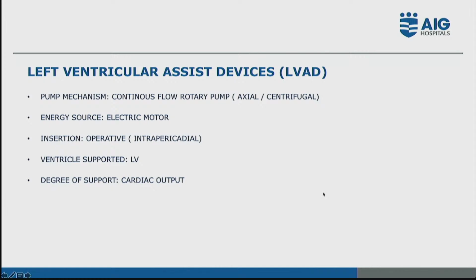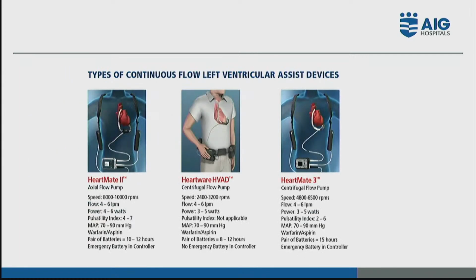So now we have completed the temporary devices. Now the long-term durable devices. First I would like to talk about left ventricular assist devices. These are again continuous flow pumps, usually implanted intrapericardially, and they provide support to the left ventricle, provide full cardiac output support, and can be managed for a long time. The commonly used devices commercially available in the market are HeartMate 2, HeartWare HVAD, and HeartMate 3. The most recent technologically advanced pump is HeartMate 3. It is a centrifugal flow pump which rotates at a speed of 5,000 to 6,000 rotations per minute and can deliver about 4 to 6 liters of cardiac output.